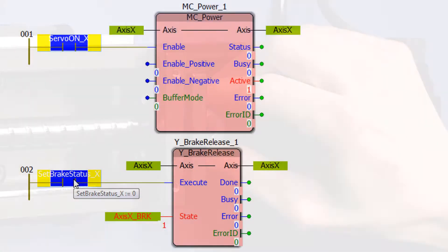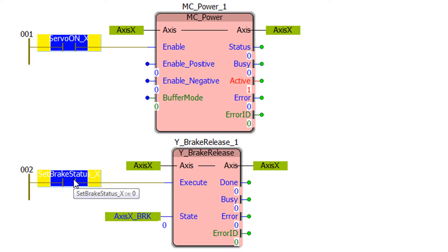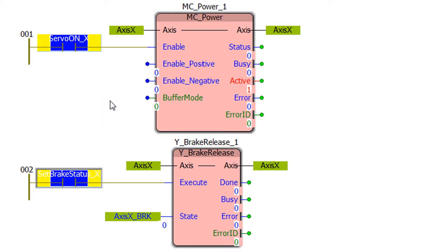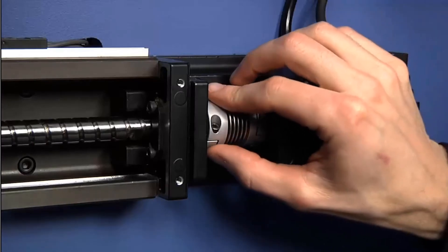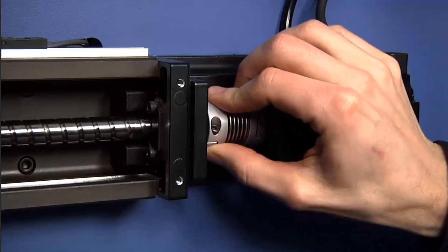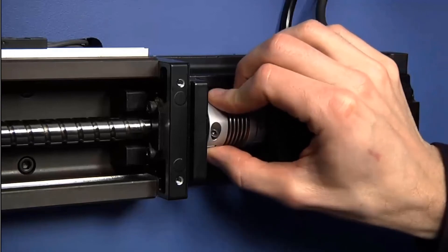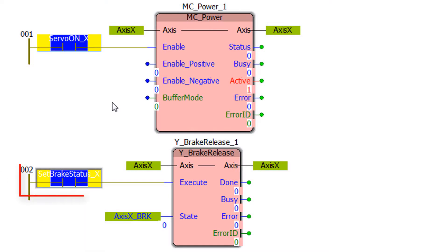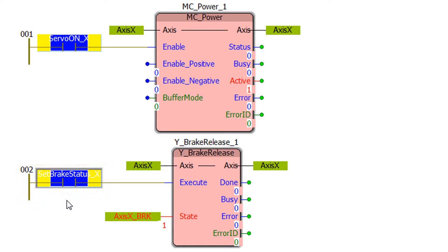Y Brake Release can also turn the brake output on and off. Each time it executes that toggles the brake state. The brake is released. The servo is off. So right now it's possible to move the shaft of the servo motor by hand. And you execute the block again to return the brake output to the engaged state and resume control with servo on.